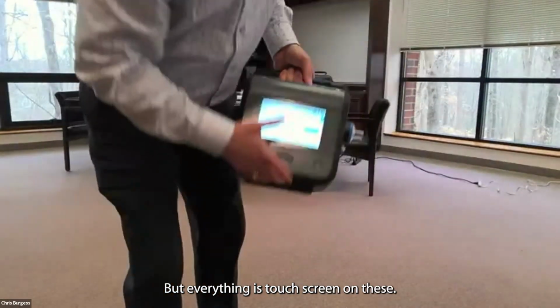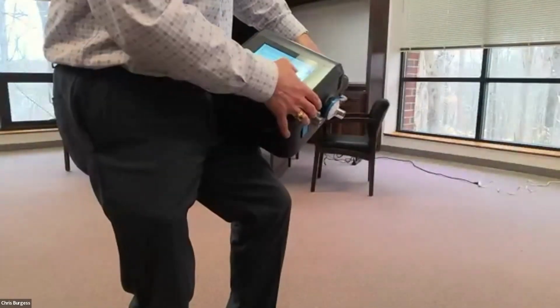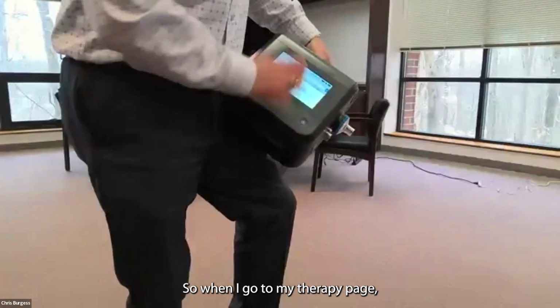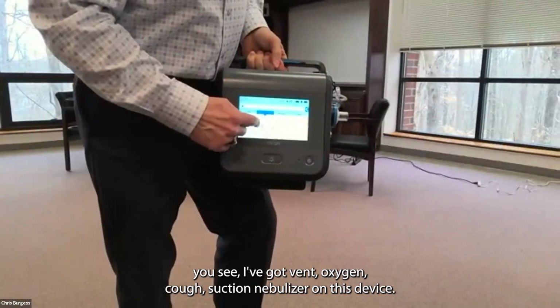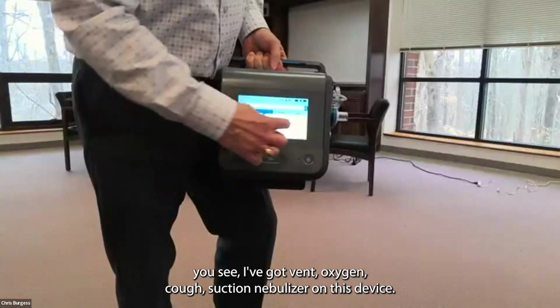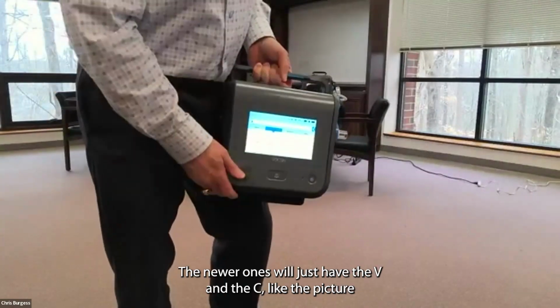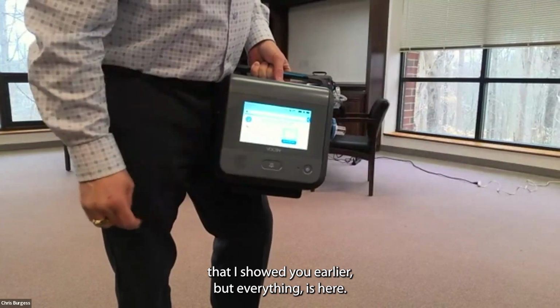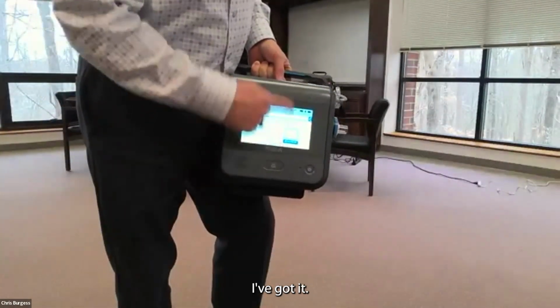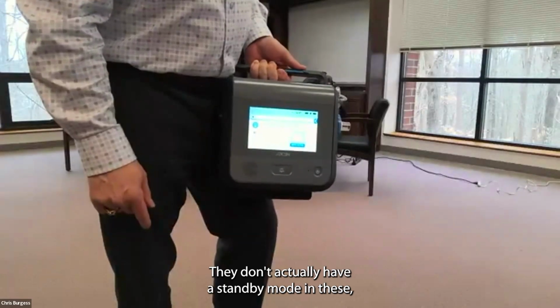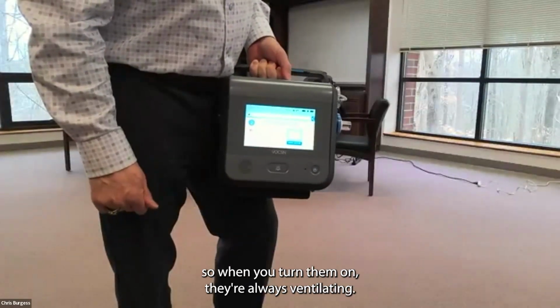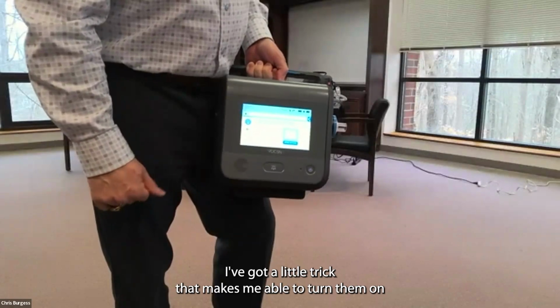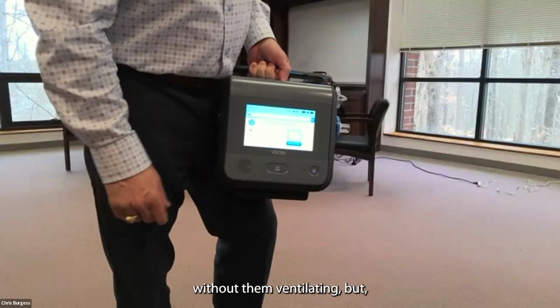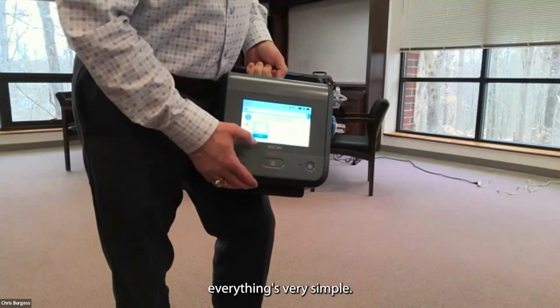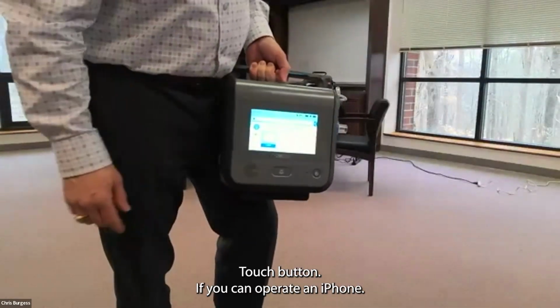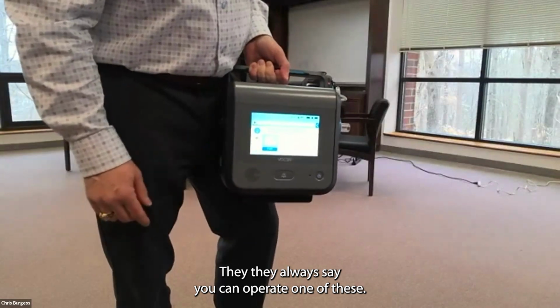But everything's touchscreen on these. Glasses off - so when I go to my therapy page, you see I've got vent, oxygen, cough, suction, nebulizer on this device. The newer ones will just have the V and the C, like the picture that I showed you earlier, but everything is here. I've got it in, I've fooled it into a standby mode - they don't actually have a standby mode in these, so when you turn them on, they're always ventilating. I've got a little trick that makes me able to turn them on without them ventilating, but everything's very simple, touch button. If you can operate an iPhone, they always say you can operate one of these.